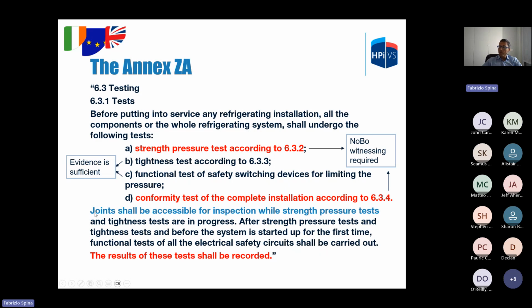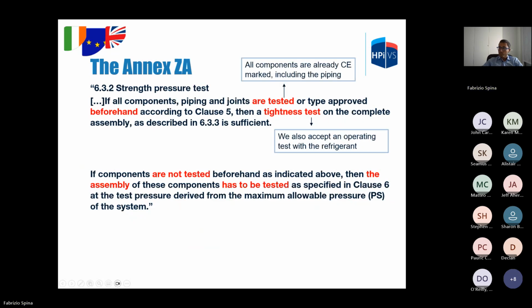Joints, especially welding joints, shall be accessible for inspection while strength pressure tests are in progress. That's to allow the inspector to verify whether there is leakage or not. The result of this test shall be recorded. So, the strength pressure test.